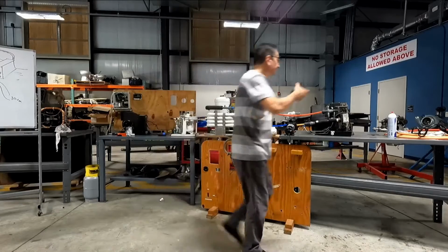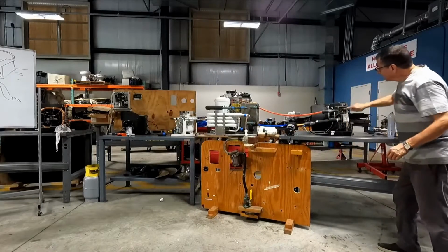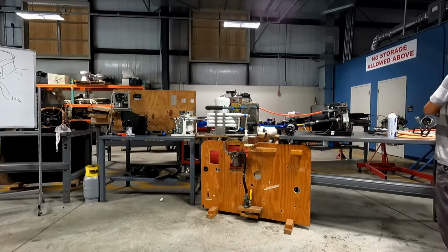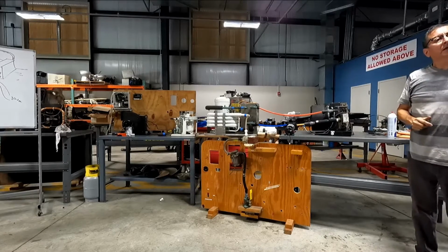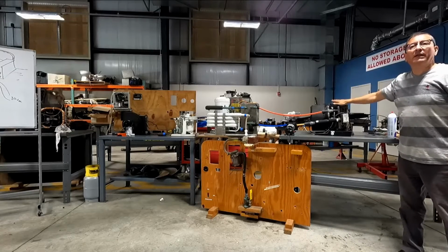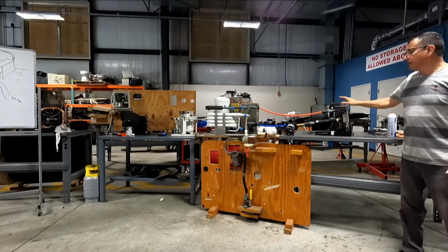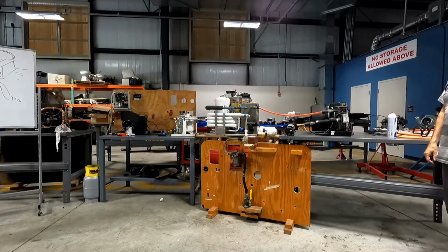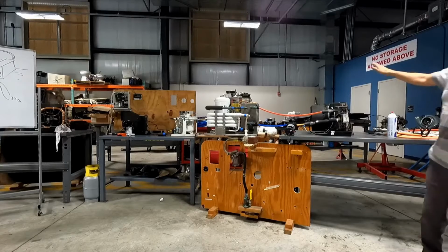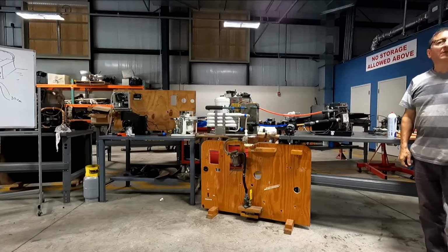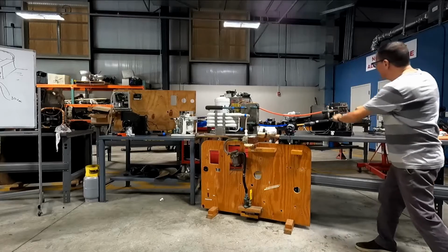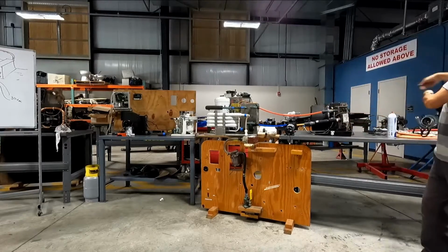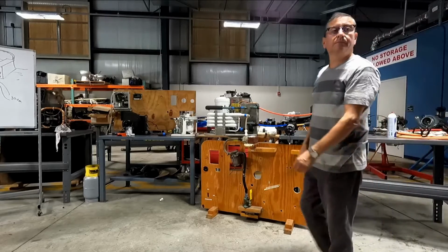Pay attention. Look, I have a T here, and I continue with other one here for other air handle, and more and more. I want to bypass this one because I need to repair this one. But I need this and this and this. Normally, you have valves here and valves here. You close the valves, you remove that unit, and everything keeps working, and the other ones are working.